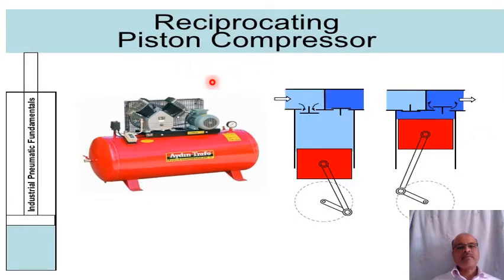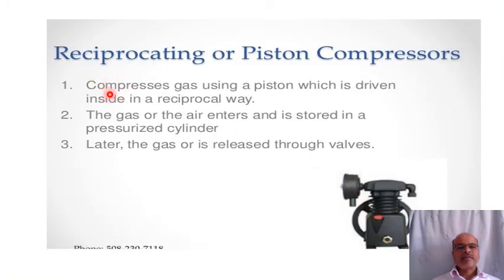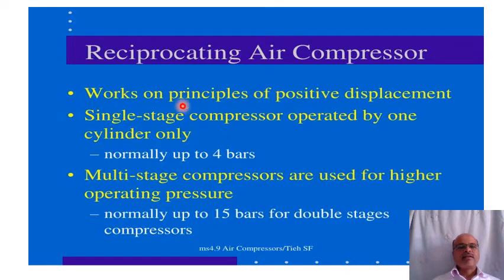The reciprocating piston compressor is shown diagrammatically. It compresses gas or air using a piston driven in a reciprocating way. The gas or air enters and is stored in a pressurized cylinder, then released through valves. It works on the principle of positive displacement. Single-stage compressors operate with one cylinder, normally up to four bars. Multi-stage compressors are used for higher operating pressures, normally up to 15 bars for double-stage compressors.